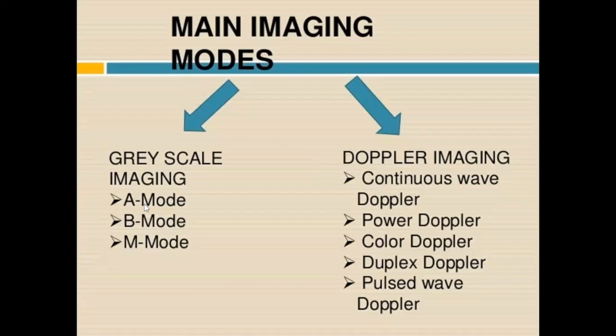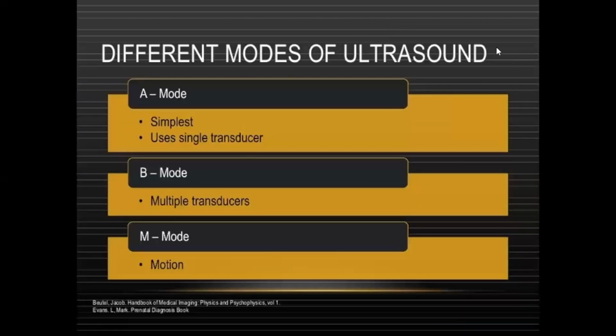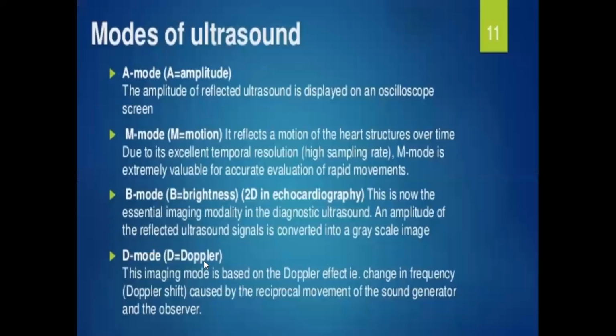Next, we go to the modes. The simple modes that we use are A mode, B mode, M mode and your Doppler mode. A mode is the simplest mode and uses a single transducer. B mode, multiple transducers. M mode is motion. More in detail, A mode is an amplitude mode. The amplitude of the reflected ultrasound is displayed on an oscilloscope screen.